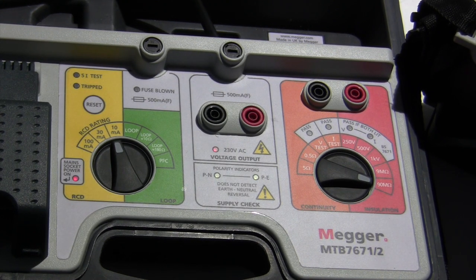And I try to test my testers. I was starting off doing it once a week. That seems to have slipped a bit now, and it's generally probably on average around once a month. But basically I hang my Fluke and my Megger off this. This squirts out some test numbers, and both the testers should come back with much the same results, certainly within the tolerance of whatever this device is putting out.